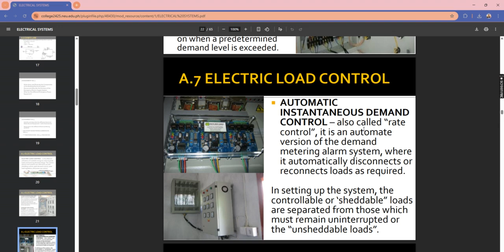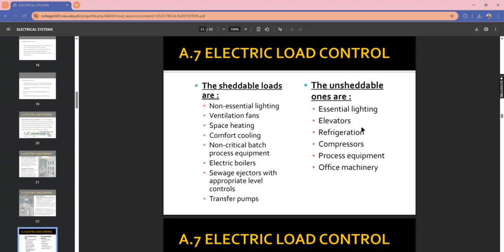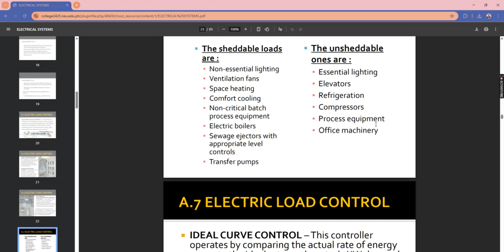Under electrical load control, the sheddable loads are the lightings, ventilation fans, space heating, comfort cooling, non-critical batch process equipment, boilers, sewage and transfer pumps, while the unsheddable ones are the lightings, elevator, refrigeration, compressors, process equipment, and office machinery. So those are the types of electric load controls that need to be continuous or non-continuous load.